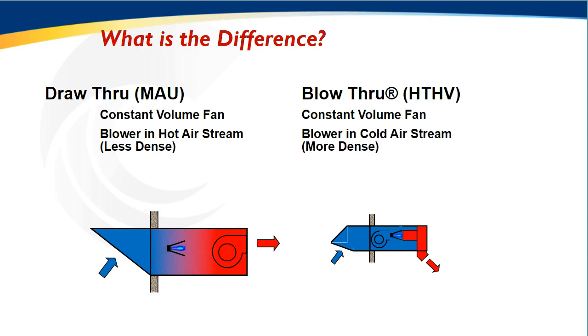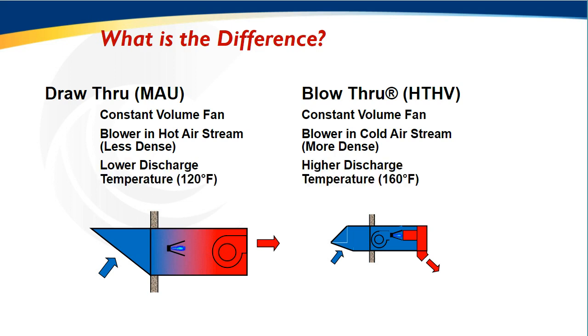And with the blow-through system, my blower is in the cold air stream such that it's processing more dense air. So when we are processing 0-degree air, higher density. And additionally, discharge temperature. Most makeup air systems, when I have the motor and the bearing and the belts in the hot air stream, they're typically limited in discharge temperature to around 120 degrees. Beyond 120 degrees, you might see belts, bearings, motors begin to fail at a higher rate.